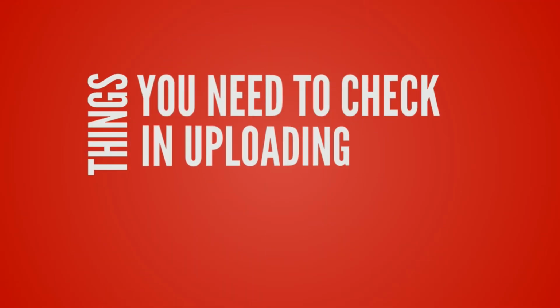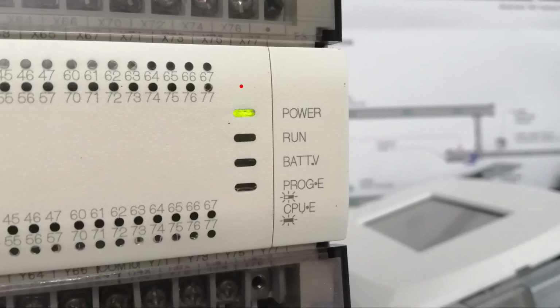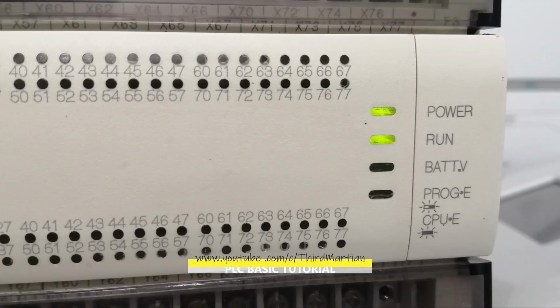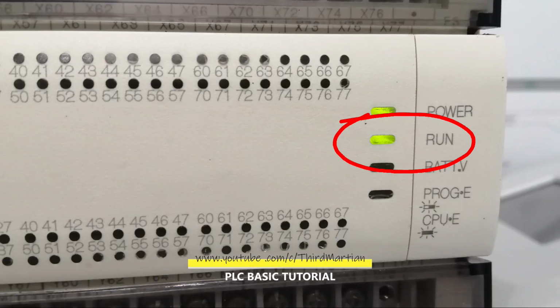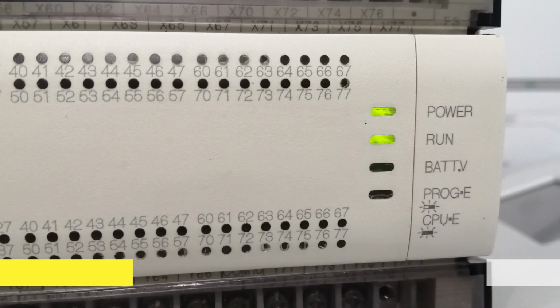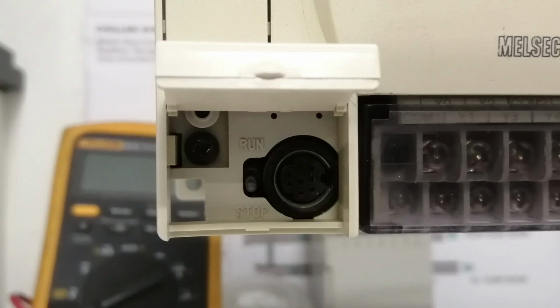Here are some factors that you should check during uploading and downloading program to the PLC, even in operation. Number 1, power indicator should be lighted. It means the PLC is powered up and it's ready to operate. Number 2, run light indicator. In run mode, the CPU is processing the inputs and outputs, solving the loaded program during each CPU scan. When downloading program in the PLC, run mode should be on. But when uploading program, run mode should be off. To do this, adjust the selector switch located beside the communication port.